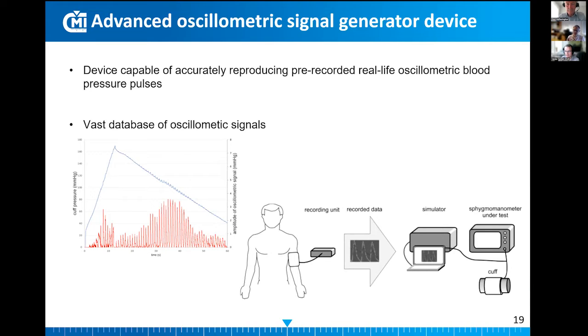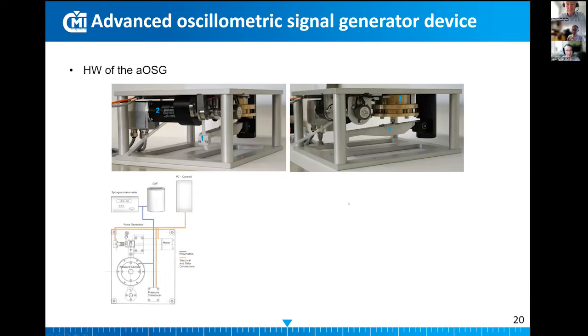This is an important part of our simulator. Beyond this, it would be only hardware, which consists of relatively few parts. The most important is the mechanism that generates these oscillometric signals to the tested devices. It consists of 3 pieces: a lever and a pressure chamber connected with a motor, and the pressure generation is done by the tested device.